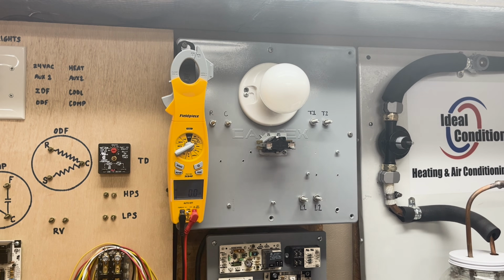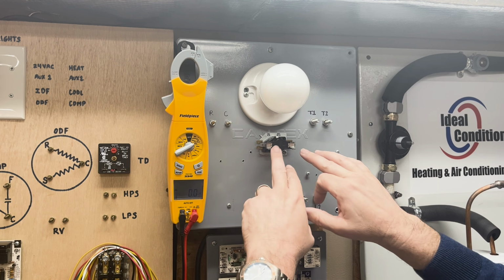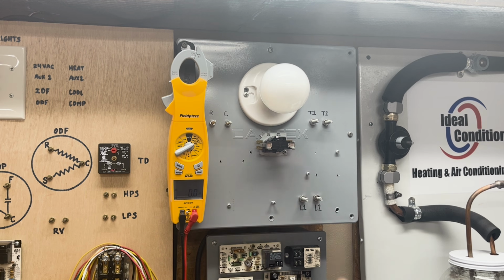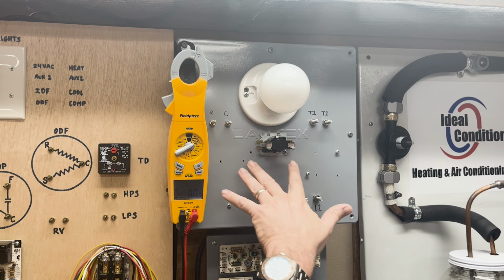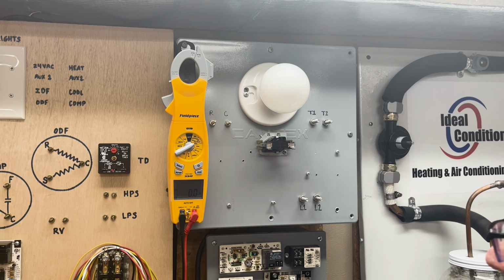So we're controlling comfort that way, and we're getting that scientifically by dropping humidity. We're collecting more moisture on that coil right in that beginning process. Same thinking was done when it was shutting off. It had to cool down before it would open up. So I'm going to show you how that works. There's no diagram on this that tells you if you're on the contact side or the coil side, so I'm going to show you how to tell the difference there.